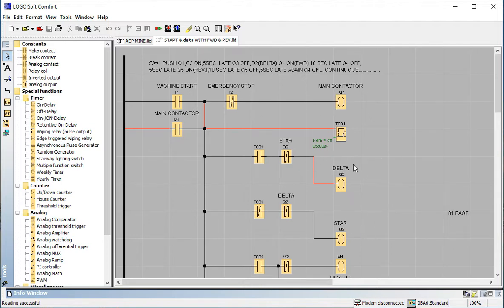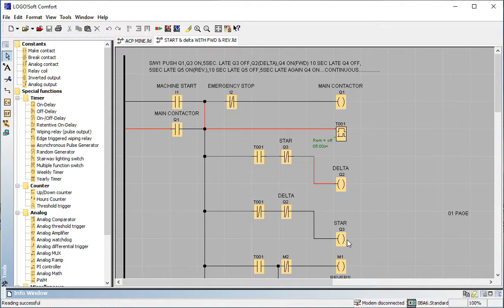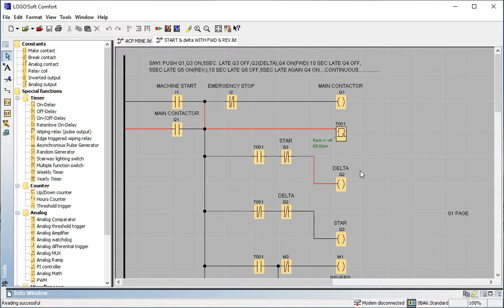This is a huge program with a start button. Q1 is the main magnetic contactor, Q3 is star, and Q2 is delta — all described here step by step. Q3 (star) has a five-second delay. When we start operation, we start in star because star has a neutral point, which limits initial current during the starting and acceleration time — from minimum to maximum level — before converting to delta for maximum speed.